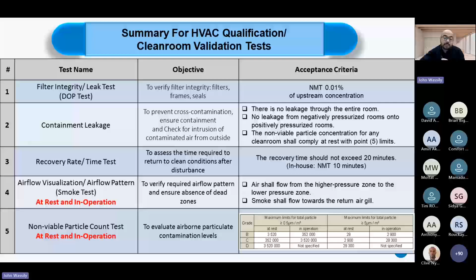Also going through the non-viable particle count, this is the test that I've been talking about on the previous slide, which is about measuring the concentration of particles corresponding to the sizes of 0.5 micron and 5 micron, because by measuring those particles, you will be sure that you are meeting the required cleanliness grade. Also, it's important to measure the viable particle count, not only the non-viable, the viable in terms of microorganisms, in order to quantify the viable microorganisms. And here we also have certain limits that we shall meet for every grade using different sampling methods.